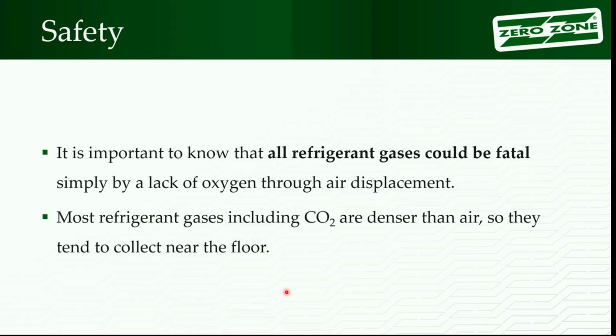The other thing you have with CO2, it's denser. All the refrigerants typically are denser than air, except for ammonia. So when they get released, they go to the floor. If you start succumbing to being asphyxiated, you hit the deck. Where do you land? On the floor. Where's a higher concentration of gas? On the floor, right? So that's kind of a double hit. So you really want to avoid that risk.